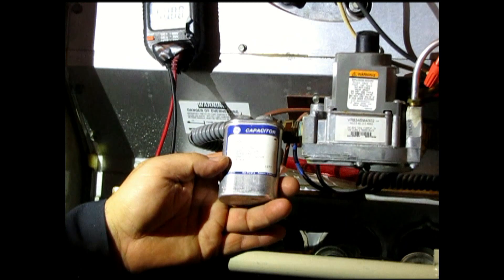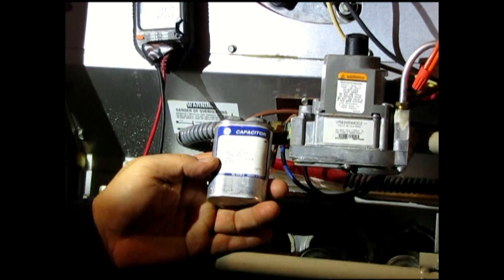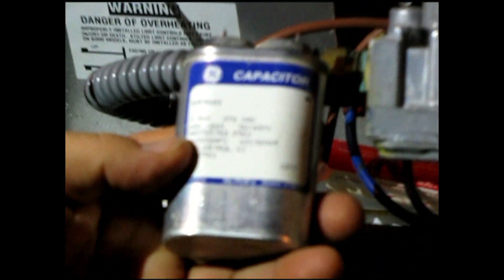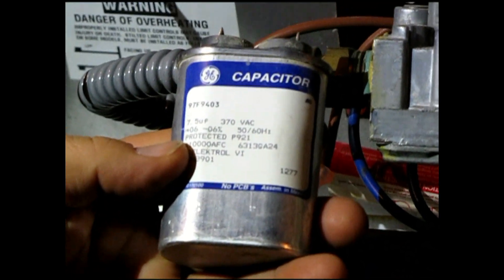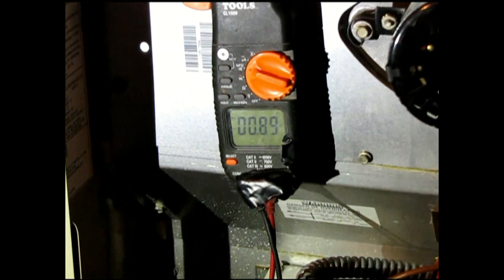So what I got here is a 7.5 capacitor to run the blower motor. It's rated 7.5 microfarads but it's reading, I can't get it focused, there it goes, 2.5.